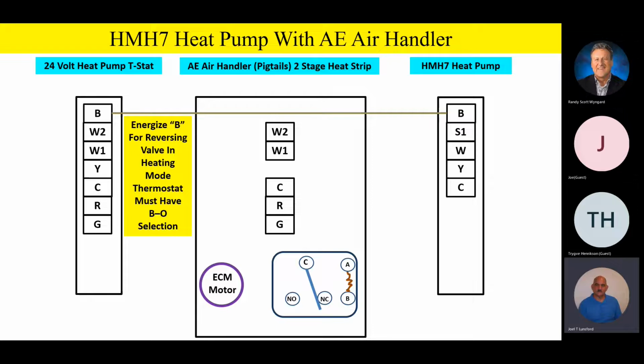Starting at the thermostat on the left-hand side, we're going to take a wire directly from B straight outside to the heat pump outside. Now, the B terminal is for reversing valve operation in the heating mode of operation. So the thermostat has to be equipped with the capability of selecting B or O for reversing valve. It should be noted, please, this is the only product we have in the inventory that we energize the reversing valve on heating. All of our other Champion heat pump products, both commercial and residential, we energize the O terminal for cooling. So this is exactly opposite.